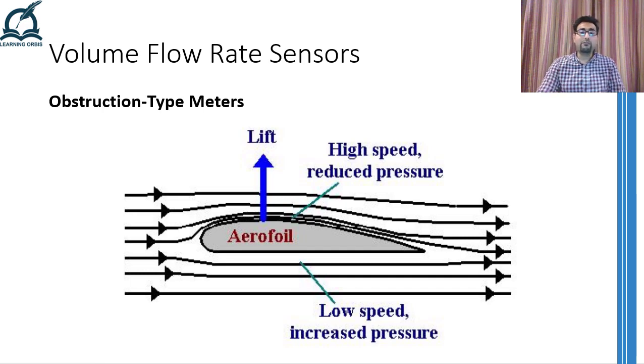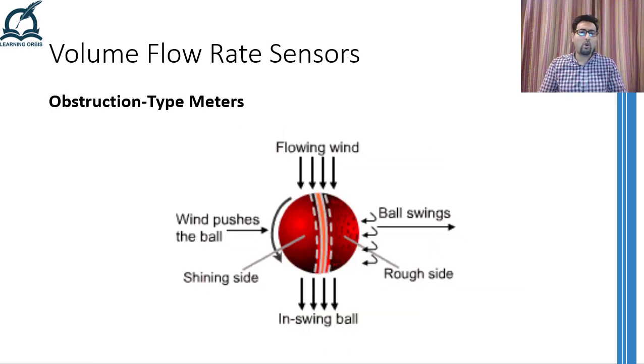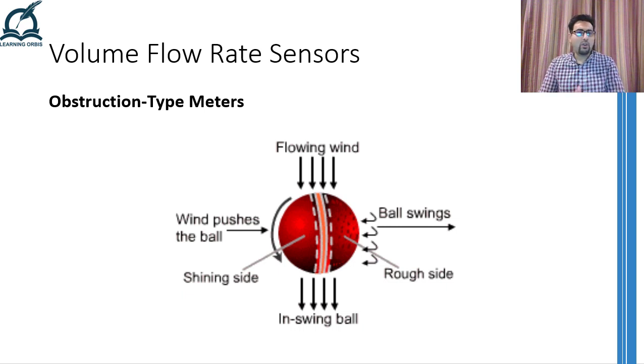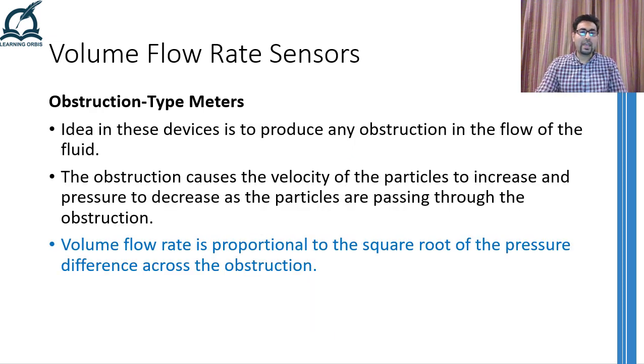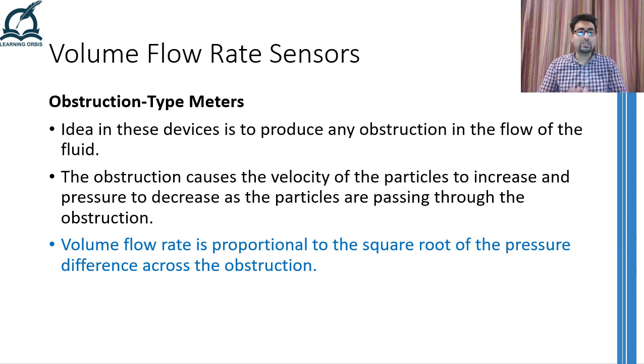This fact is responsible for creating an uplift when an aeroplane is running on the runway and hence is able to fly. Moreover, the same reason is behind a baseball ball or a cricket ball swinging when it is delivered by the bowler. So all the obstruction type meters are going to increase the speed of the flowing fluid, which will cause its pressure to drop. The volume flow rate can then be measured by measuring the pressure difference across this obstruction. In fact, the volume flow rate is proportional to the square root of the pressure difference across the obstruction.